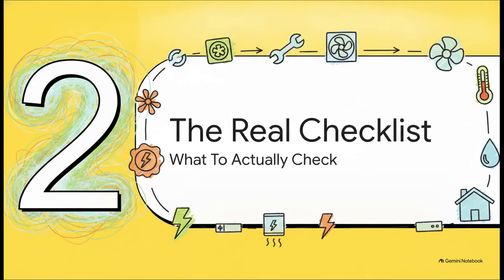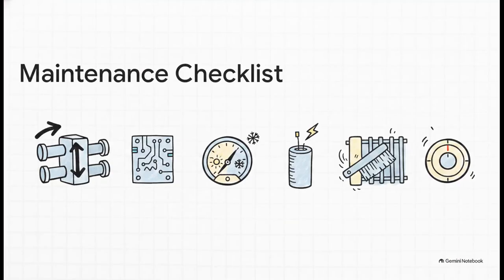Moving right along to Section 2, the real maintenance checklist. So the crucial point is, what does a worthwhile maintenance visit actually look like? Well, a proper visit must cycle the reversing valve in both directions just to make sure it switches cleanly. They absolutely must test the defrost sensor so it triggers only when necessary. And they have to measure your refrigerant charge in both heating and cooling modes. Why is that a big deal? Because the system can actually run perfectly fine in one direction, but be completely undercharged and straining the compressor in the other. They also need to inspect electrical components like the capacitor, clean the outdoor coil, and calibrate the thermostat. Literally every single one of these steps is non-negotiable.